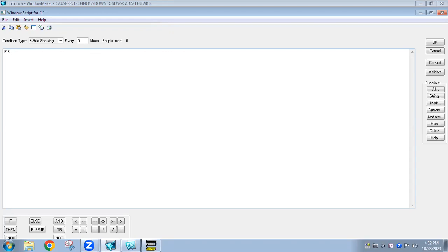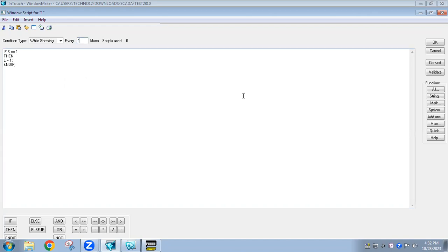I am writing: if the switch tag name 'S' — since it is a condition I have to use double equals — equals 1, then the lamp should get on. For the assignment statement it should be single equals with a semicolon: L = 1. Since we started with an if statement we have to close with end-if. This script will run every one millisecond — that is the scanning time. I'll click OK.